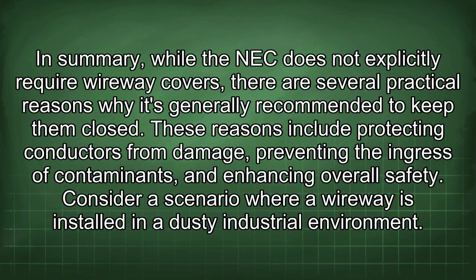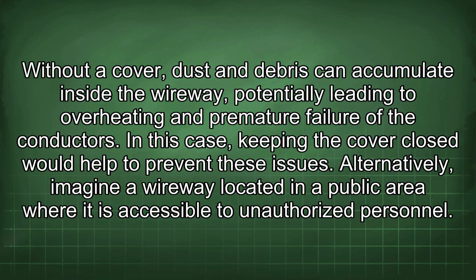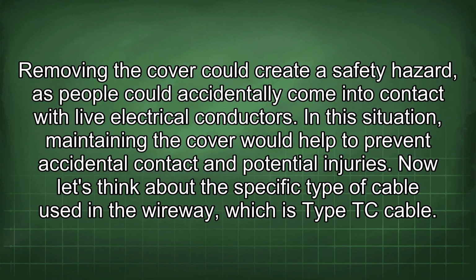Consider a scenario where a wireway is installed in a dusty industrial environment. Without a cover, dust and debris can accumulate inside the wireway, potentially leading to overheating and premature failure of the conductors. In this case, keeping the cover closed would help to prevent these issues. Alternatively, imagine a wireway located in a public area where it is accessible to unauthorized personnel. Removing the cover could create a safety hazard, as people could accidentally come into contact with live electrical conductors. In this situation, maintaining the cover would help to prevent accidental contact and potential injuries.